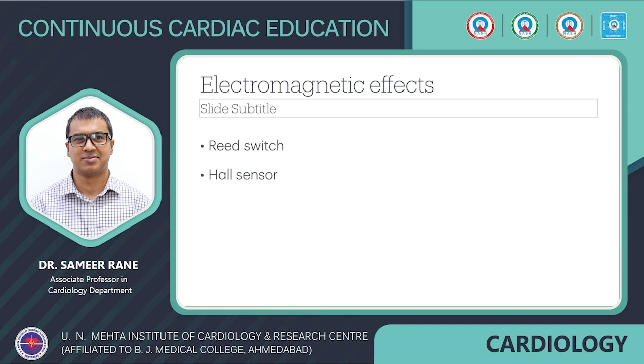The static magnetic field can activate the reed switch, leading to asynchronous pacing and inhibition of the tachytherapies. The high electromagnetic interference can lead to power on reset, when the device reverts to default factory settings. EMI can also lead to oversensing and delivery of inappropriate therapy from misinterpretation of EMI as a tachyarrhythmia, or EMI can lead to oversensing and cause a decrease in pacing, leading to bradycardia.